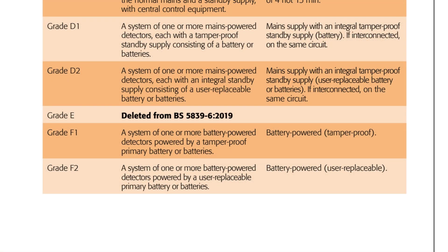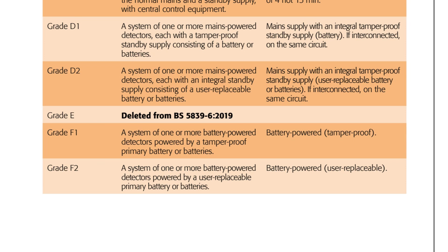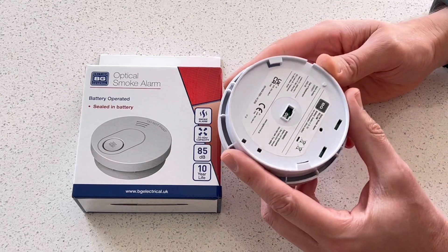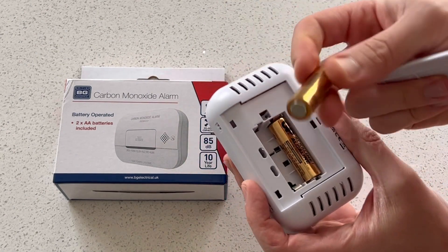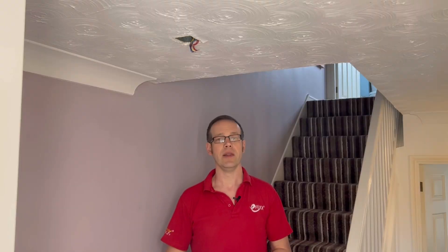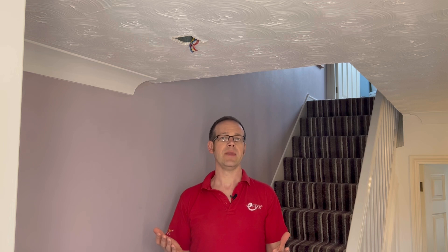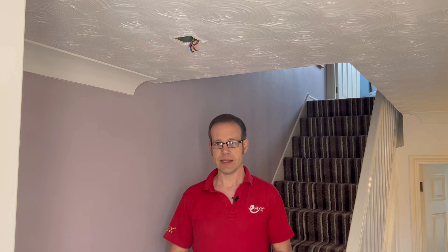Grade E went the same way as Grade B and was deleted in the 2019 update of BS 5839-6. Grade F again splits into two subsets, F1 and F2, with similar characteristics to D1 and D2. The F1 system is a system of one or more battery-powered detectors powered by a tamper-proof primary battery or batteries, and the F2 is a system of one or more battery-powered detectors powered by a user-replaceable primary battery or batteries. The one key difference between Grades D and F is that the F grades are powered only by batteries, with no mains power whatsoever.